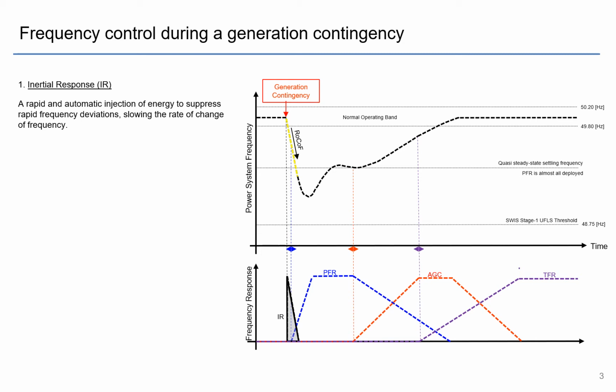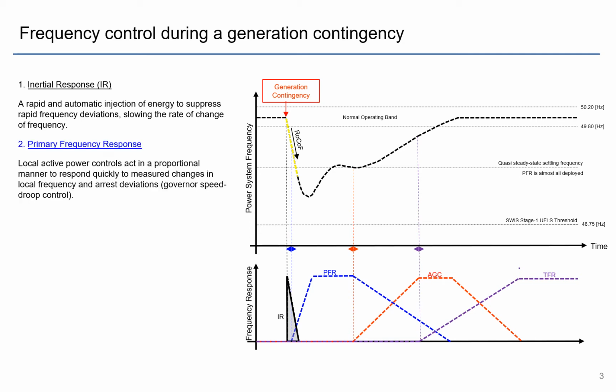So the frequency starts to decrease and will keep on decreasing until the system collapses, were it not for primary frequency response. Primary frequency response is local active power controls that act in a proportional manner. So it's local to the generating units, and they respond to frequency deviations and are there to arrest frequency deviations. Usually these are things like governor speed droop controls. Here we see primary frequency control come into play, and we see the minimum frequency point, which we call the frequency nadir. And then it usually settles at what is called the quasi-steady state settling frequency, or the QSSF. At that point, all of the primary frequency response, or almost all, has been deployed, and it just sits there because that's the droop deviation.